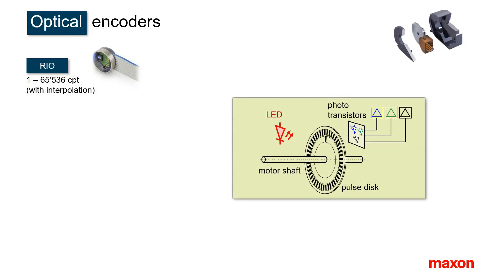Optical incremental encoders are the most accurate encoders in the Maxon portfolio, due to the high resolution and often direct sensing without interpolation. In optical encoders, the light of an LED passes through slits in a pulse disk mounted on the rotating motor shaft, and is detected by phototransistors directly producing the high and low states of the encoder channels. The RIO is an extremely small optical encoder that uses a reflective optical principle with signal interpolation to achieve very high resolution.